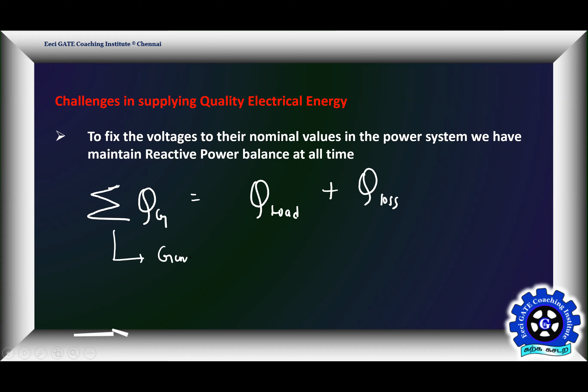So this reactive power can be generated by whom? It can be generated by generators, capacitors, and various other devices like phase modifiers, var generators. Okay. So all this reactive power generated by all the elements connected in the power system should be equal to the reactive power load. This reactive power is mainly used by induction motors, transformers, transmission lines. Okay. So all other inductive loads, they require reactive power. And even the reactive power losses occur in the transmission lines.